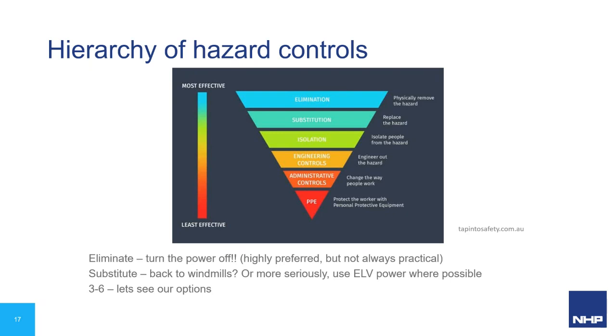Substitute, so you can go back to windmills, grindstone, that sort of thing. Or more seriously, use ELV power where possible. By ELV, I mean below 50 volts. Usually 50 volts DC is what we see. A lot of mine sites, et cetera, use that sort of approach. So all the controls on the front are all 24 volts DC, and it's only 240, 415 right at the back of the cabinet where it has to be, to minimize where those arc faults can actually occur.